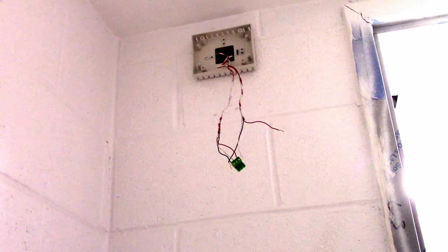So I'm trying to show you, it's hard to see. The negative right here is going to the chassis, and the positive is going to the power from the transformer on a 24 volt circuit. So this is a polarity device, and it's important because it's got a certain type of communication with the system. Apologize for the lighting, it is what it is.